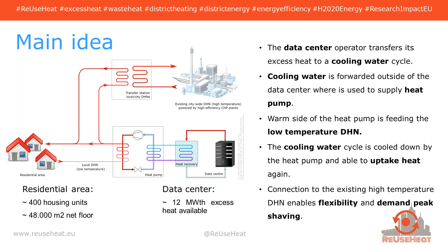The low temperature district heating network is under construction right now; there was no district heating network before this project. The cooling water cycle is cooled down by the heat pump and is then able to pick up heat from the data center again. There is also a connection to the high temperature district heating network to ensure flexibility and demand peak shaving.